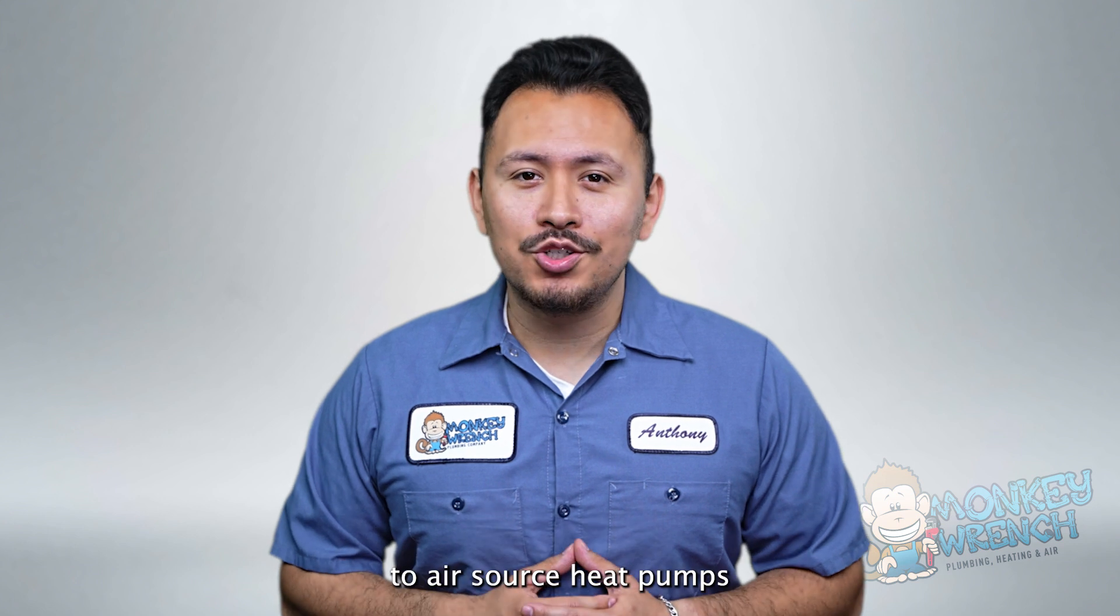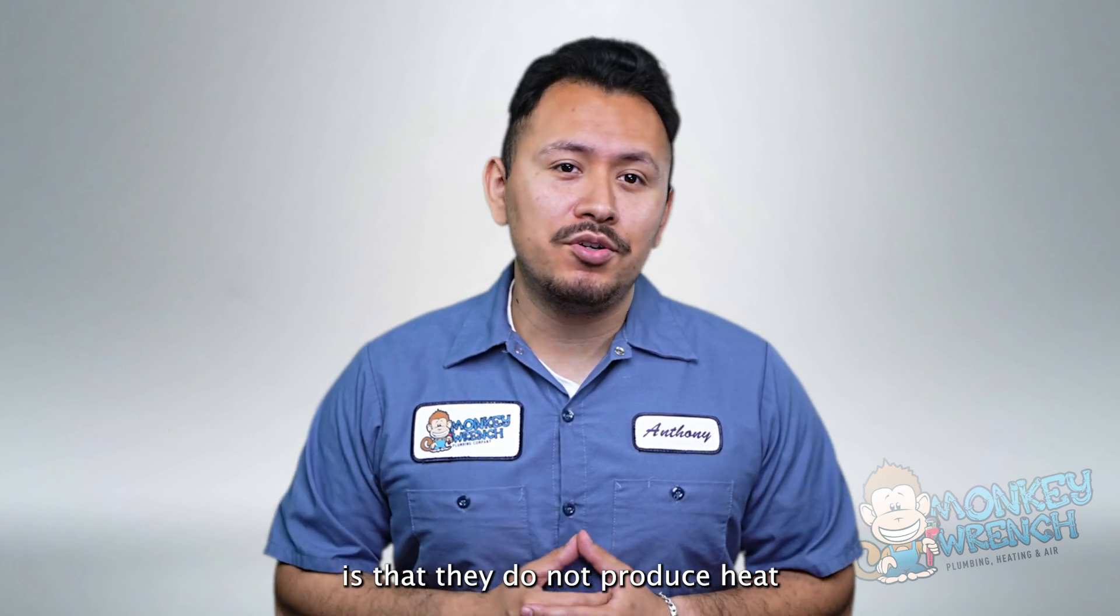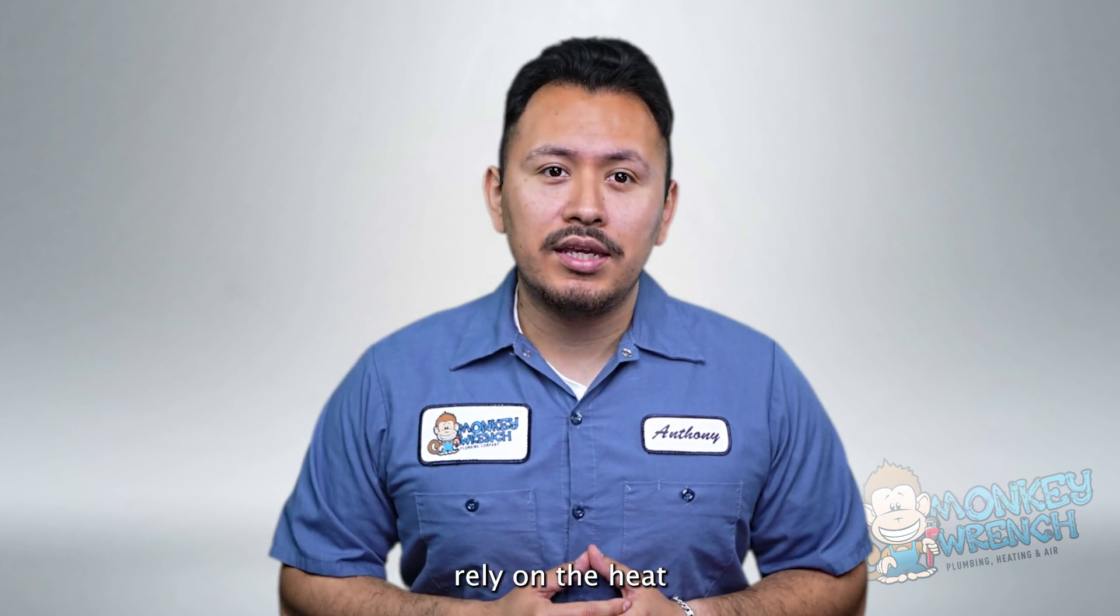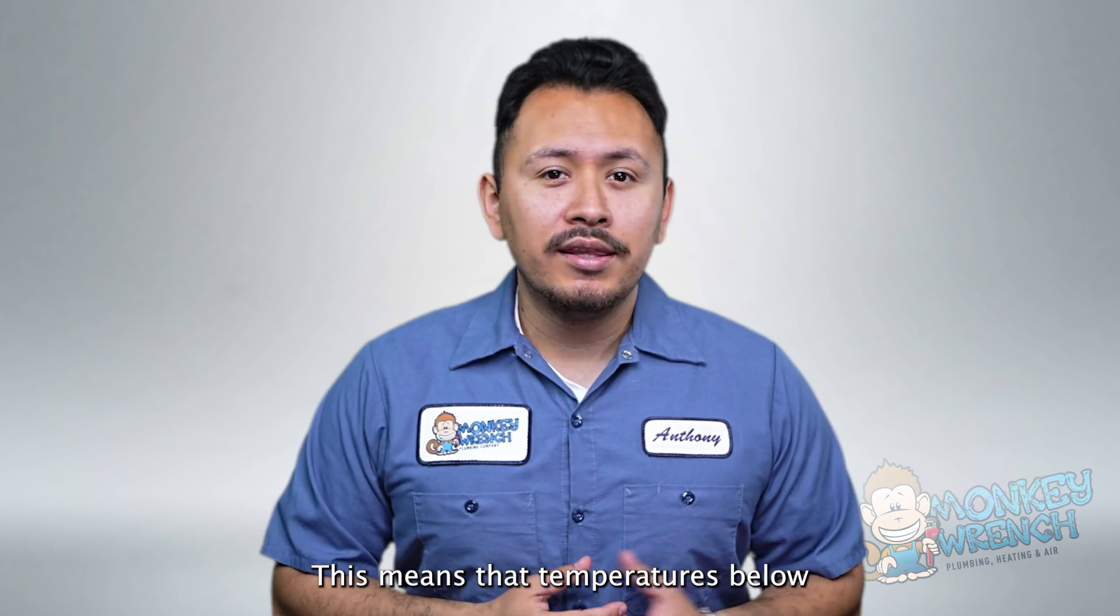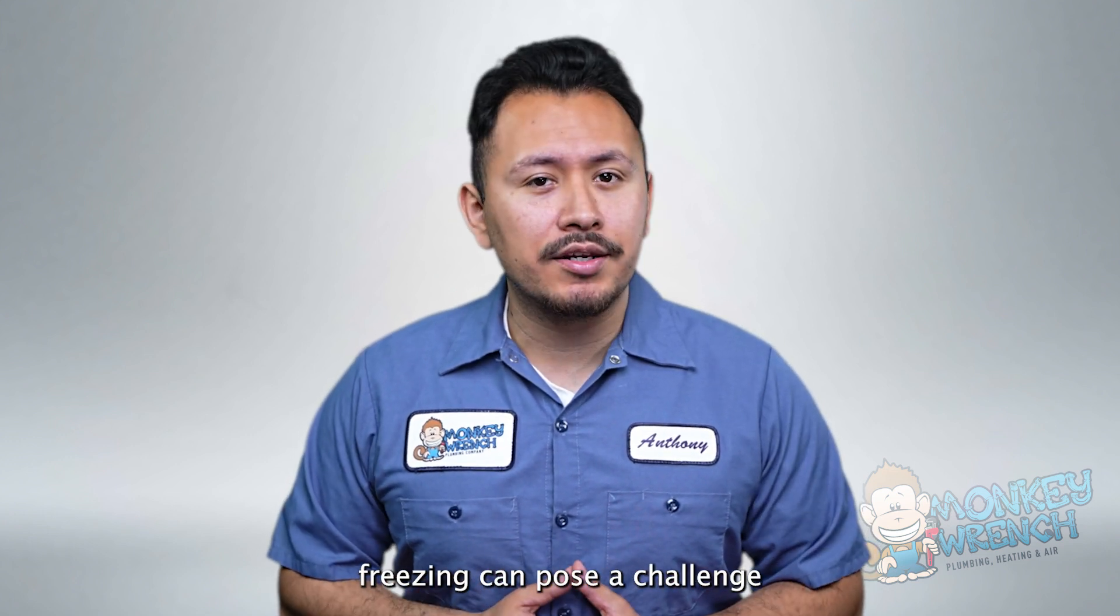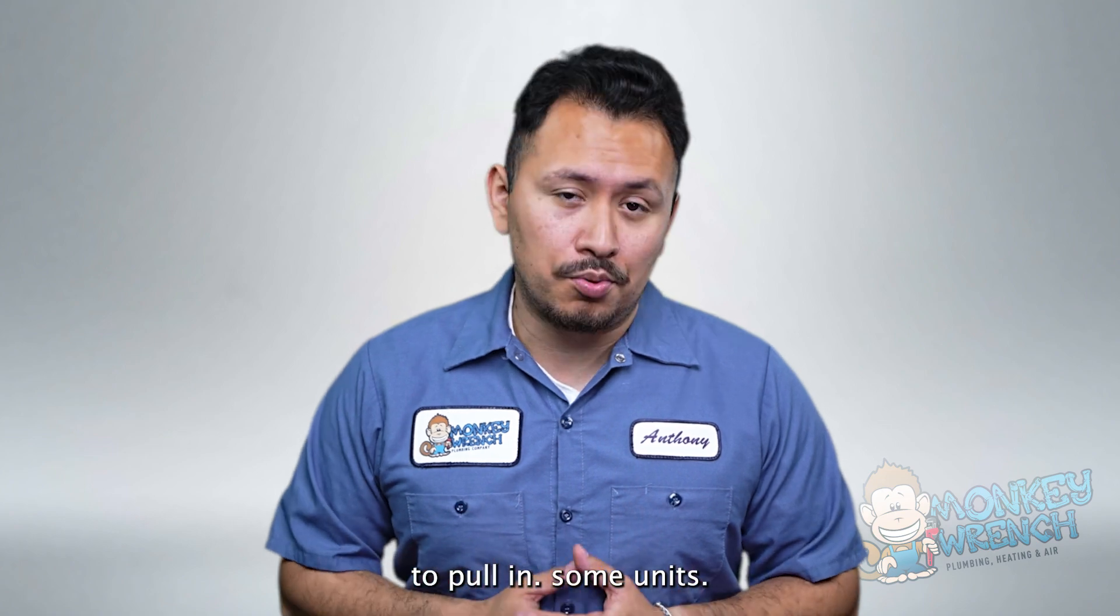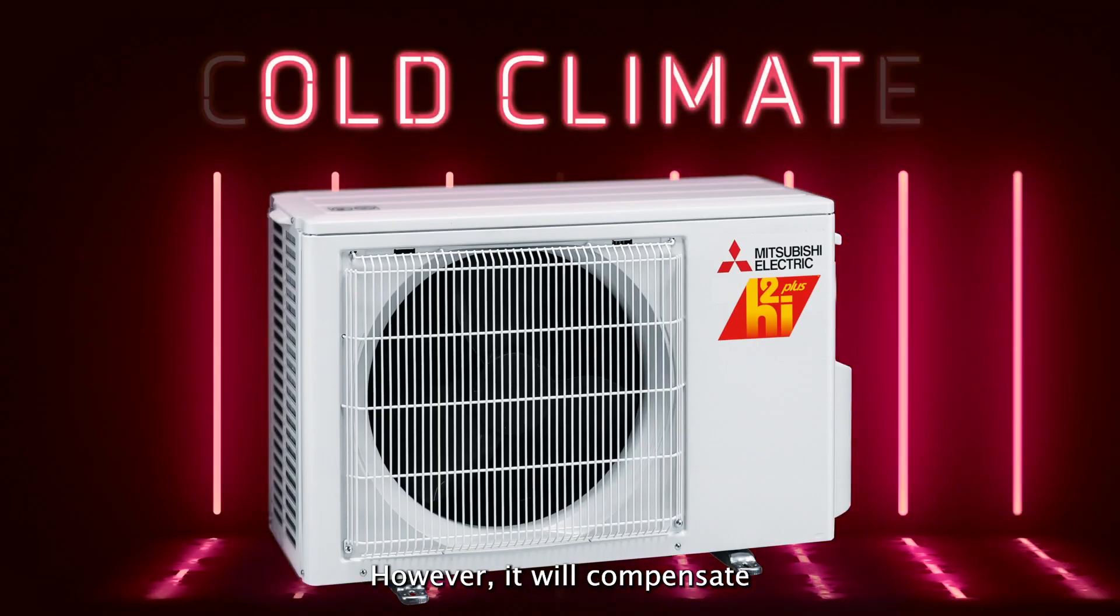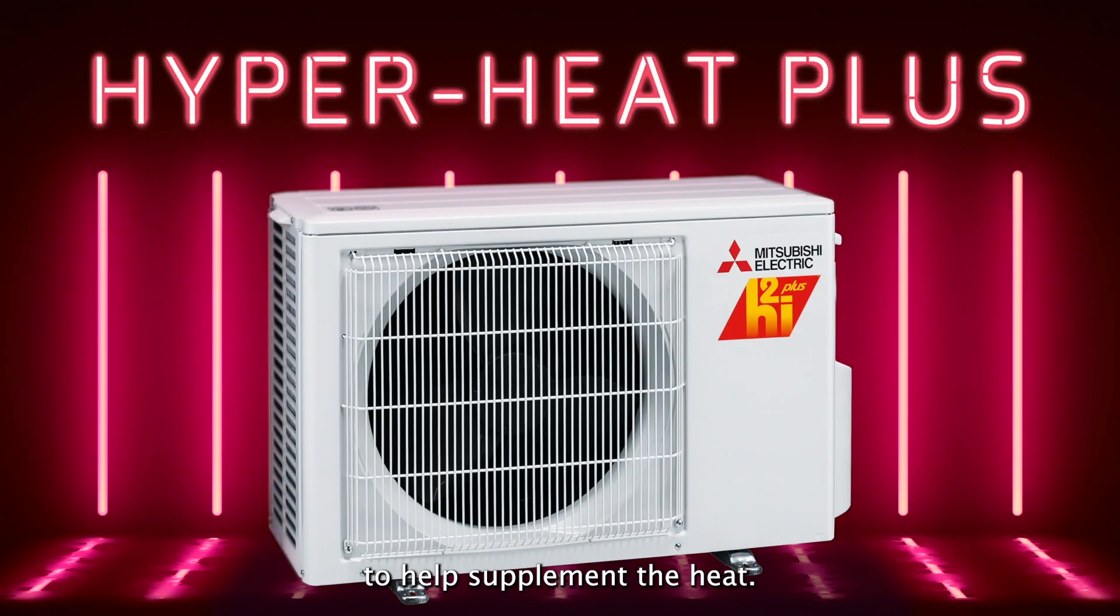A notable point to air source heat pumps is that they do not produce heat and instead rely on the heat from the outside to warm a home. This means that temperatures below freezing can pose a challenge to heat pumps since there is less heat to pull in. Some units however will compensate by adding a heating element to help supplement the heat.